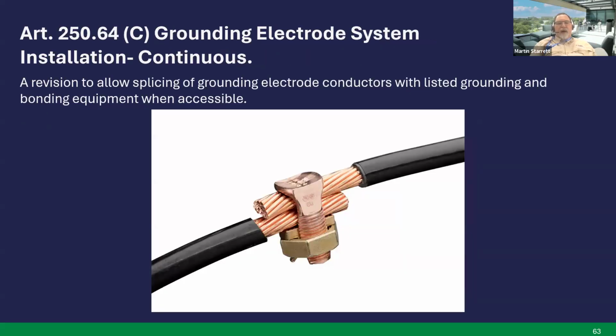Next slide. Article 250.64(C), grounding electrode conductor installation, continuous. A revision to allow splicing of grounding electrode conductors with listed grounding and bonding equipment when accessible. So if you see this picture of a split bolt, if this connection is accessible and that split bolt is listed as grounding and bonding equipment, you can use that. No irreversible crimp, no CAD welding. Of course, that's code minimum; if your engineer requires it, you'll have to do that. But if this split bolt is listed and it's accessible, you can use it. Next slide.